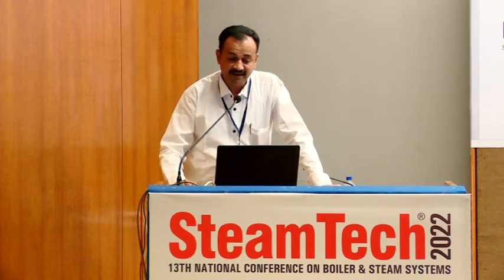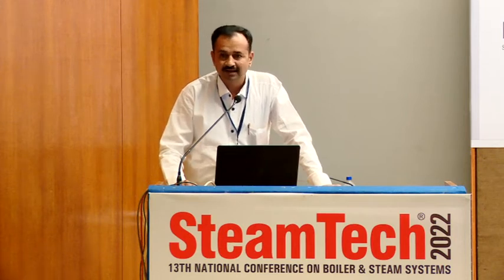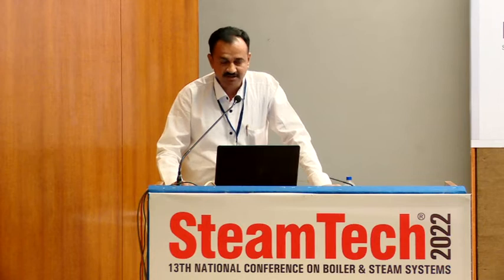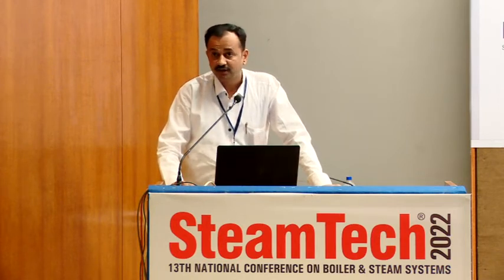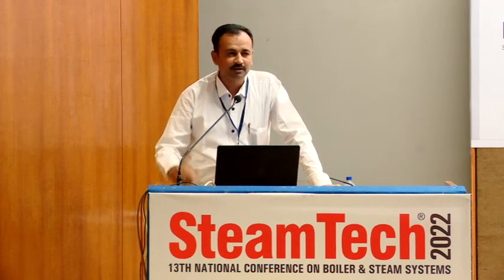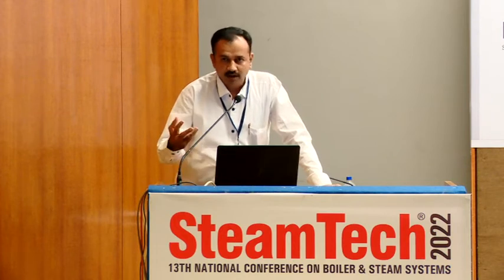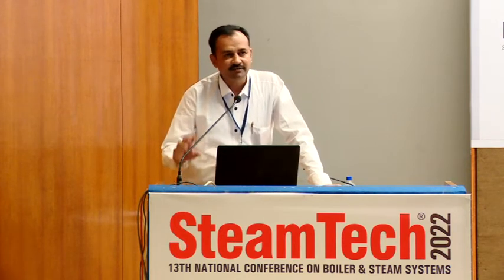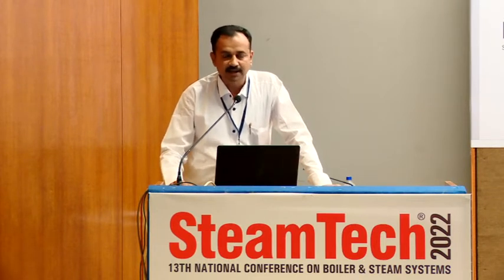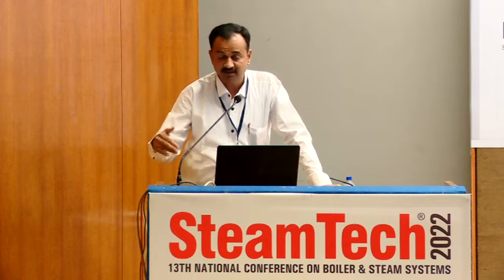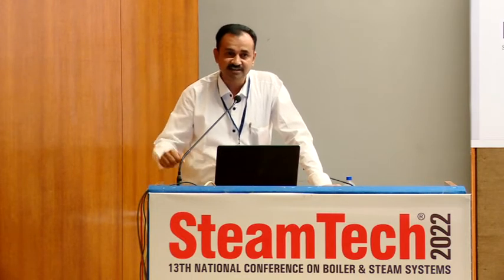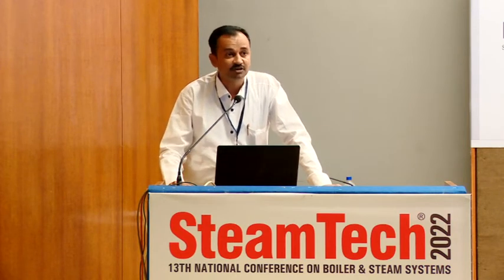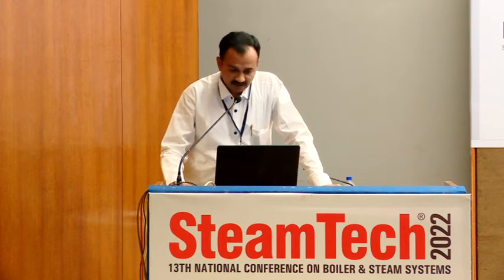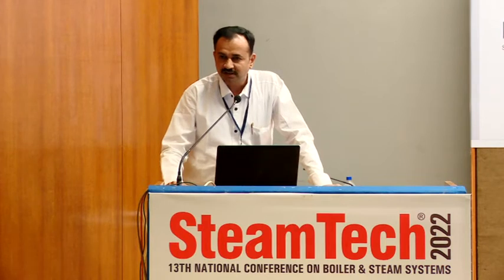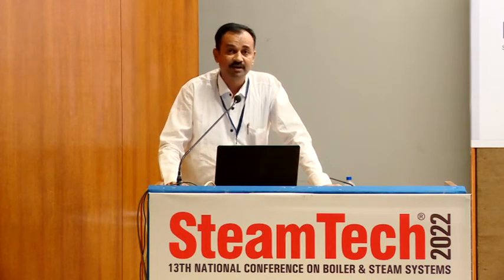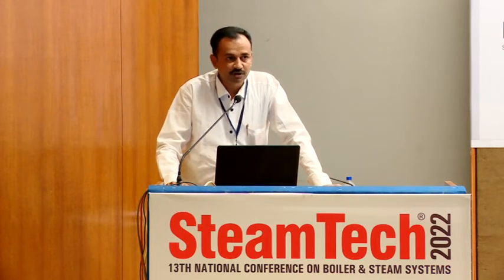So if I break down the operation cost for a solid fuel boiler, generally, as Mr. Vyas said, it is in the tune of 50 to 60%. So let's say you are procuring a 5-ton boiler for roughly 1 crore or 1.25 crore, operating at a 3-ton average load. Your fuel cost will be yearly in the tune of 5 crore rupees, roughly. That is as per today's price rise, or the last month's price rise, of around 13 or 15 rupees for Indonesian coal. So this is how fuel cost dominates on the solid fuel boiler side. The rest of the costs are maintenance cost and electricity cost, all of them will be there. But fuel cost is the major cost from the user's point of view, and the user is more worried about that.